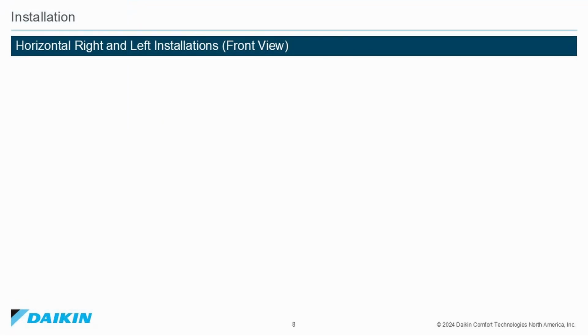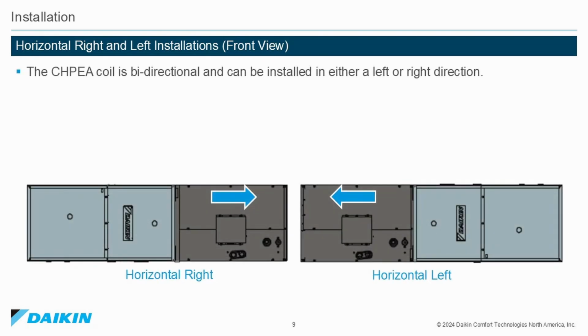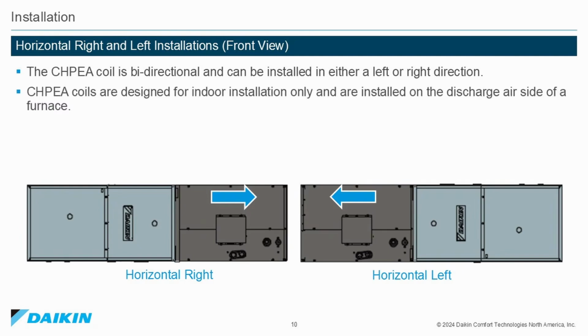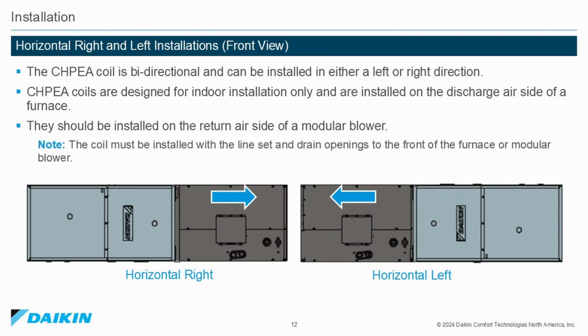Front view. The CHPEA coil is bidirectional and can be installed in either a left or right direction. CHPEA coils are designed for indoor installation only and are installed on the discharge air side of a furnace. They should be installed on the return air side of a modular blower. Note: the coil must be installed with the line set and drain openings to the front of the furnace or modular blower.